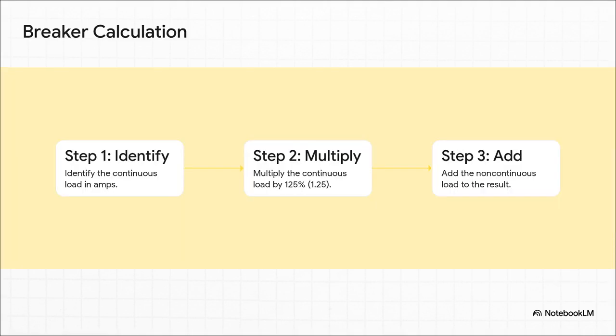So, how does this actually work in the real world? The calculation is surprisingly simple. First, you figure out your continuous load in amps. Second, you multiply that number by 125%, or just 1.25 on a calculator. This is what builds in that crucial safety buffer. And finally, you just add any non-continuous load to that number to get your minimum required breaker size.